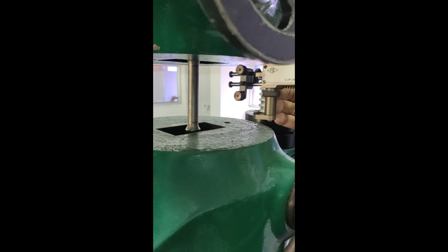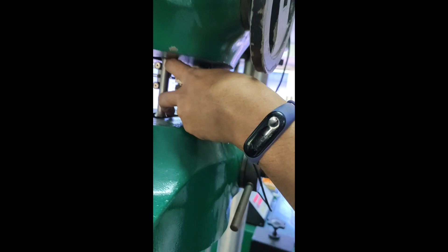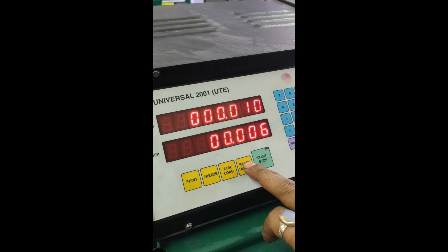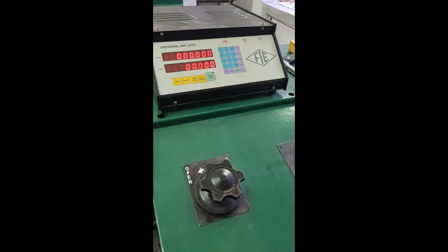I will fix the extensometer on this material specimen like this. While putting the extensometer, it should be done in such a way that the specimen and extensometer are perfectly aligned. Otherwise, it will give erroneous results. So for that, we will hold it properly and then we will fix it. This converts the voltage signal into physical units, so we will make everything 0. Now we can go for the actual test.